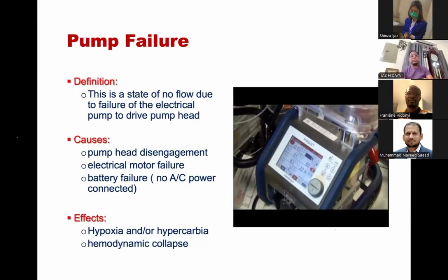The third is battery failure. No AC power is connected and your machine is running on the battery, and sometimes through the ignorance of the bedside ECMO specialist, ECMO nurse or ECMO physician, the AC power connection with the console is ignored, and the time will come when your battery gets drained and the machine is going to be off. This is called battery failure. So no AC power, no battery backup available. The causes of pump failures can be pump head disengagement, electrical motor failures, or battery failures, meaning no AC power connected.